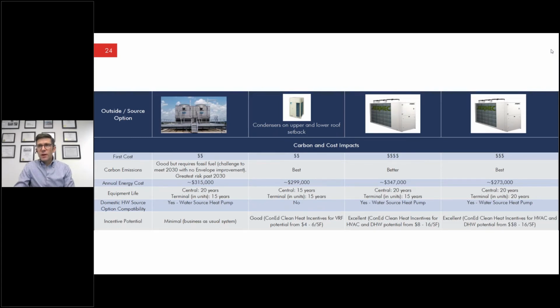We often look at water source systems. I will say with a water source system, you need a heat addition source to that loop. Your condenser water loop needs a heat source to do all your heating from it. What we've found challenging is what is that source if you're trying to do all electric. There are options. First off, if you're at a different site, this building wasn't going to be able to do geothermal given the existing building location. If you can do geothermal, ground source, that's a great solution, and we do that elsewhere. That's one answer.